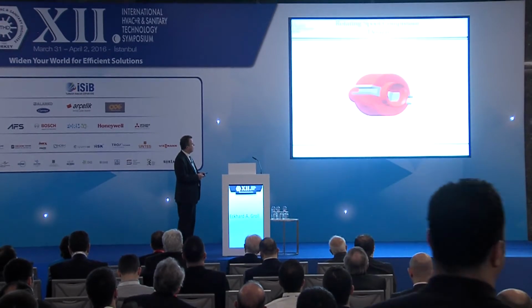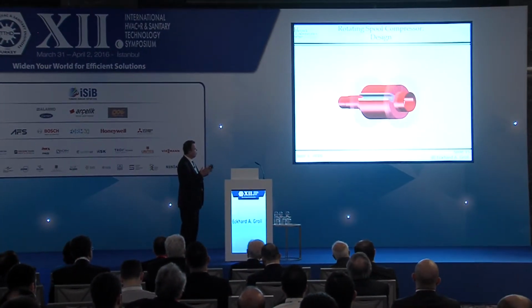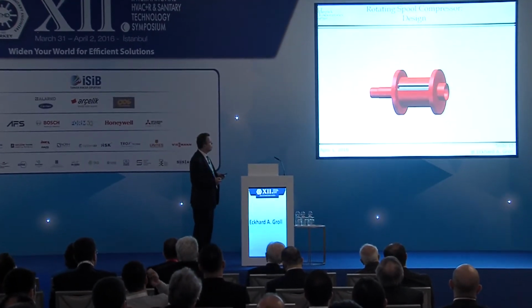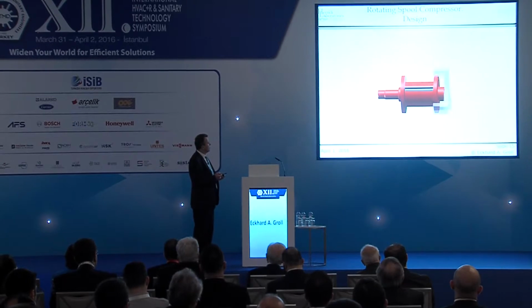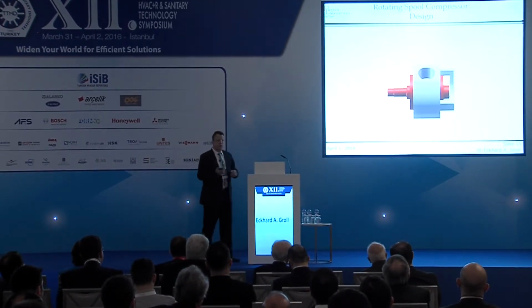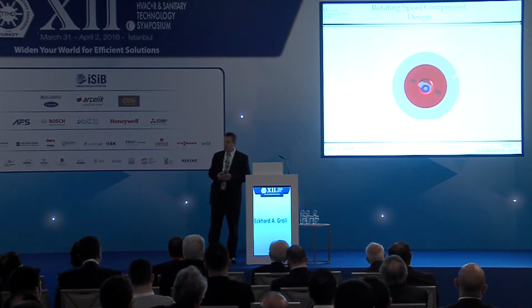Right? So, as you see, there is an end plate on both sides, which moves the sealing surface to the surface of the rotating end plate against the housing, and that has some distinct advantages. If you can run the animation, it will show you a little bit of how this compressor is made up. You have the shaft and the cam together with the vane. The vane rotates with the spool, and then that is put into the spool end plates that also rotate with the spool, and ultimately we put a housing around it with a suction and a discharge port, and you have the spool compressor.